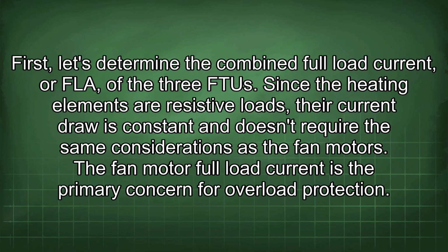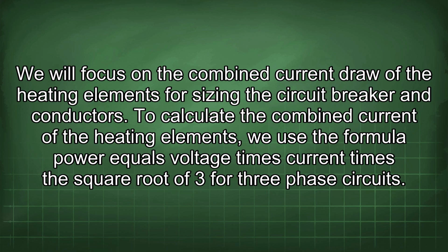First, let's determine the combined full load current, or FLA, of the 3 FTUs. Since the heating elements are resistive loads, their current draw is constant and doesn't require the same considerations as the fan motors. The fan motor full load current is the primary concern for overload protection. We will focus on the combined current draw of the heating elements for sizing the circuit breaker and conductors. To calculate the combined current of the heating elements, we use the formula power equals voltage times current times the square root of 3 for 3-phase circuits.